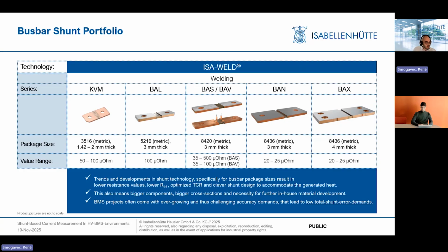So since we are speaking about high voltage, we will be speaking about busbar shunts, only because of the high currents that are going on in this sense. We have different sizes, all in metric format. Thicknesses are from roughly 1.5 millimeters to 4 millimeters, and resistance values from 20 to 500 micro ohm. Mostly, in most cases, customers need 100 micro ohm or 20 when the nominal current really exceeds 600 amps RMS.